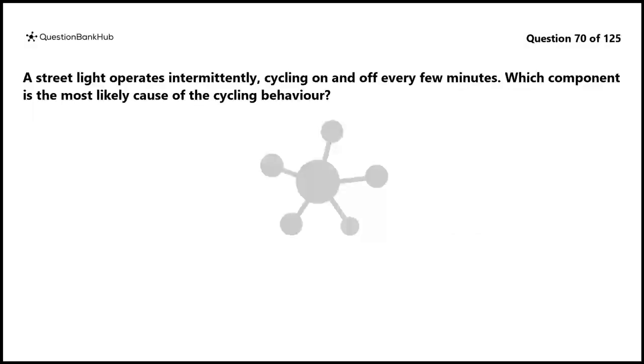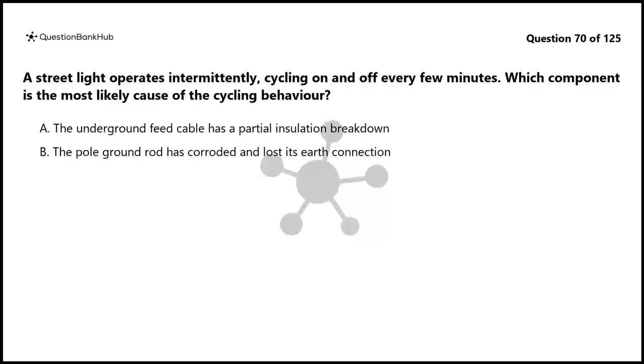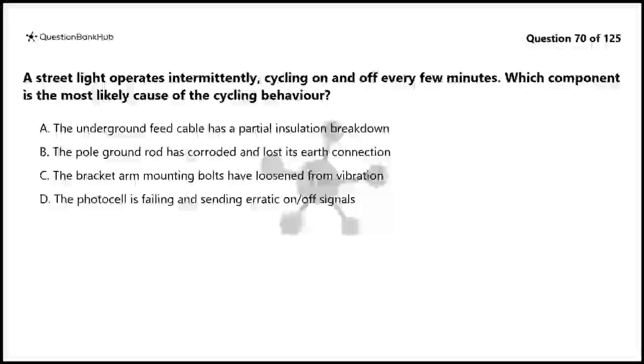Question 70. A street light operates intermittently, cycling on and off every few minutes. Which component is the most likely cause of the cycling behavior? A. The underground feed cable has a partial insulation breakdown. B. The pole ground rod has corroded and lost its earth connection. C. The bracket arm mounting bolts have loosened from vibration. D. The photocell is failing and sending erratic on-off signals.